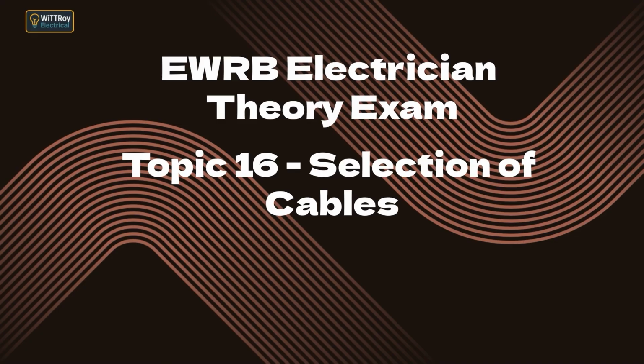16b. Provide examples and explain how a cable is chosen for a stated application considering all of the above factors. When choosing a cable for any application, the same structured process must be followed. You start by identifying the design load and determining the installation conditions. This allows you to select the correct installation table for the cable type and method. Then you consider all derating factors, temperature, grouping, and insulation, and apply them to the cable's current carrying capacity. You ensure that after derating, the cable can still carry the required load.